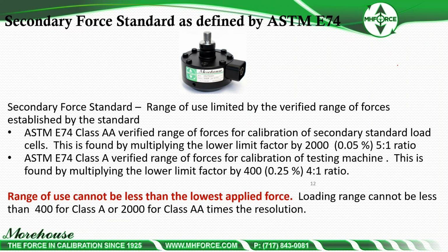Secondary force standard, the range of use is limited by the verified range of forces established by the standard. ASTM E74 Class AA verified range of forces for calibration of secondary standard load cells. It's basically found by multiplying the lower limit factor by 2,000. And this gives us a 5-to-1 ratio.